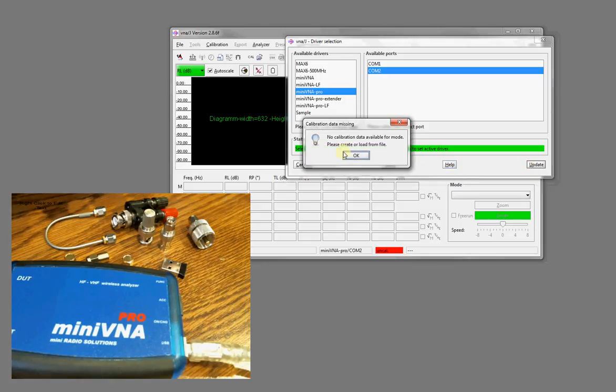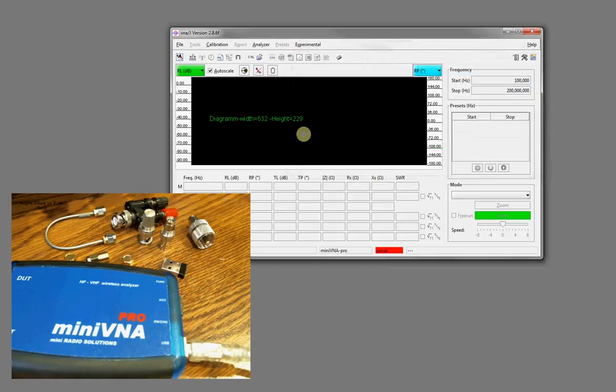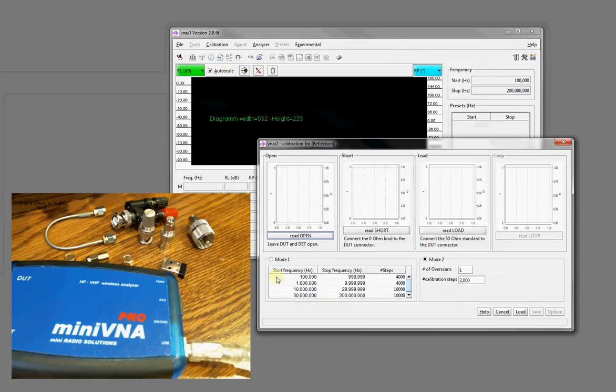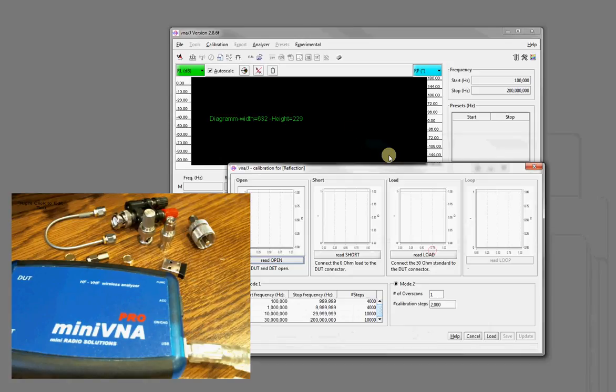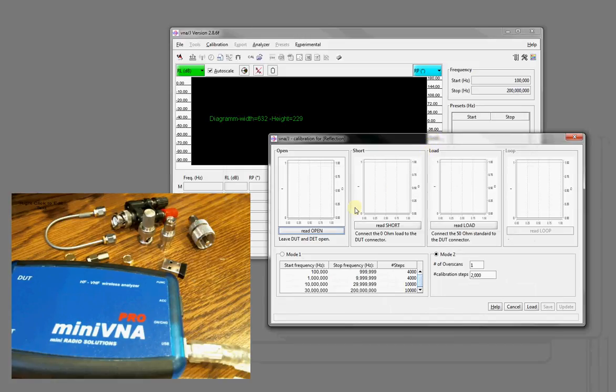And there's a warning I got when I first loaded the software. No calibration data available for mode, because we haven't calibrated the unit yet. So we're going to hit OK. The next thing we want to do is create a calibration file for it. So we're going to hit Create, and another window pops up here. And you'll see that it's read open, read short, read load, and you'll see that read loop is not active because we're not in transmission mode right now. We're in reflection mode. And you know you're in reflection mode because it defaults to reflection mode when you start up the software. So we're going to start from left to right.